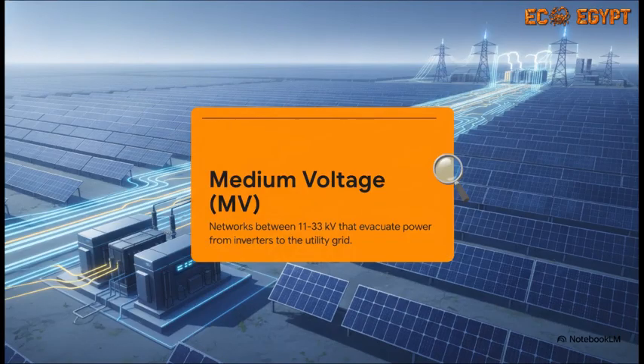So, to really get how a power plant ticks, you first have to understand the different leagues, I guess you could say, of electricity it handles. Medium voltage in a PV plant typically operates anywhere from 11 up to 33 kilovolts. And this network has one massive, absolutely vital job. It is the primary power evacuation path. It takes the energy straight from the inverter step-up transformers and acts as this heavy-duty transmission highway, carrying all that power directly out to the utility grid.